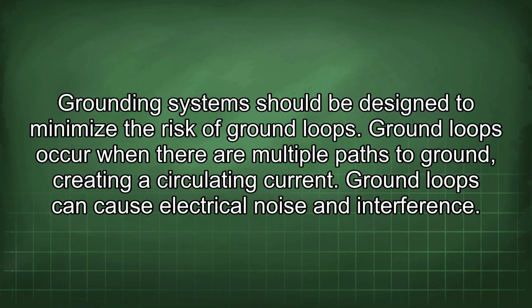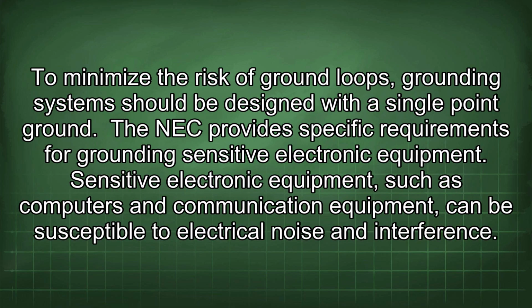Grounding systems should be designed to minimize the risk of ground loops. Ground loops occur when there are multiple paths to ground, creating a circulating current. Ground loops can cause electrical noise and interference. To minimize the risk of ground loops, grounding systems should be designed with a single-point ground.